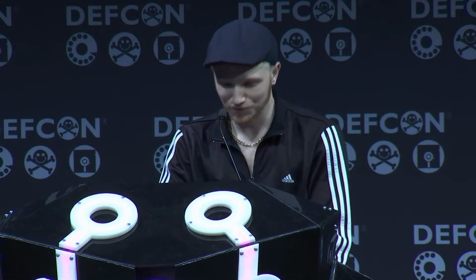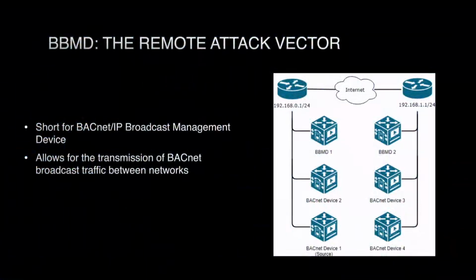This looked pretty grim at first because we were using broadcast traffic, and that typically doesn't travel over the internet. But thankfully, a certain BACnet technology came to save the day, and that is BBMD, or BACnet IP Broadcast Management Device. A real tongue twister, but suffice it to say, it allows for the transmission of BACnet broadcast traffic, exactly the kind we're using, over the internet between different networks.